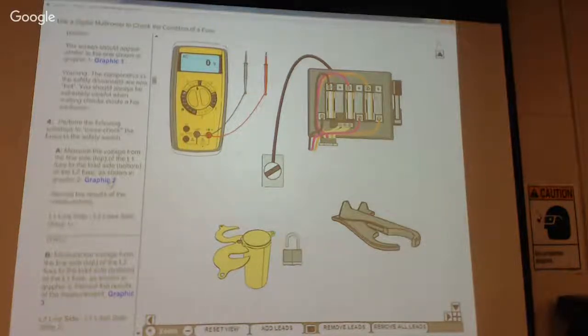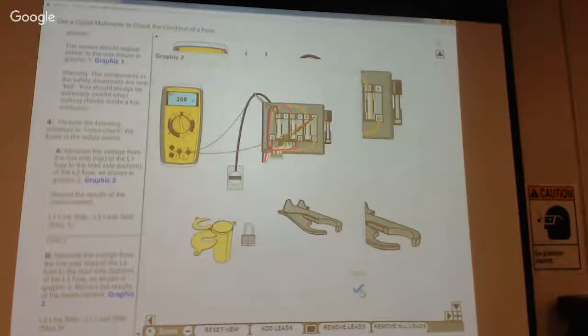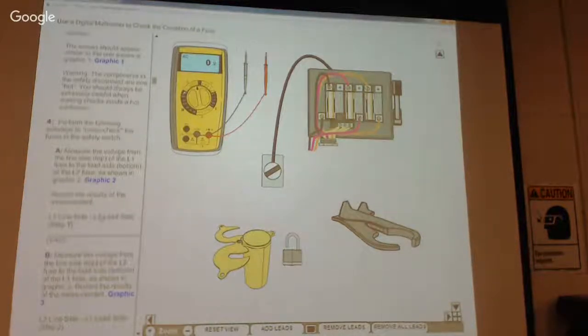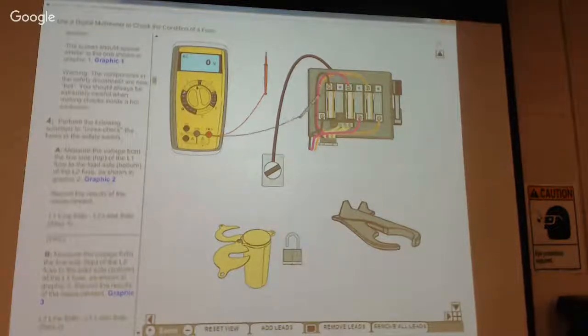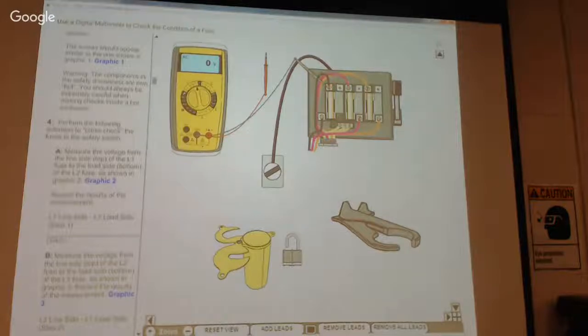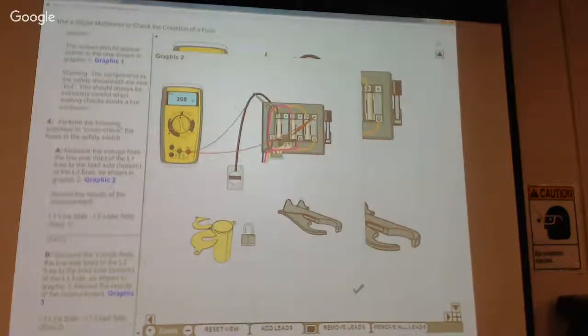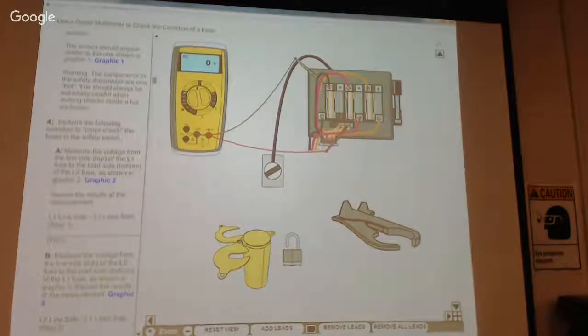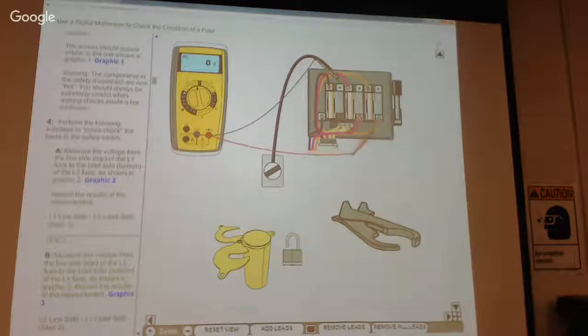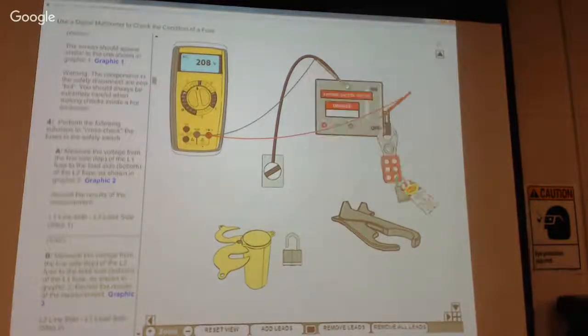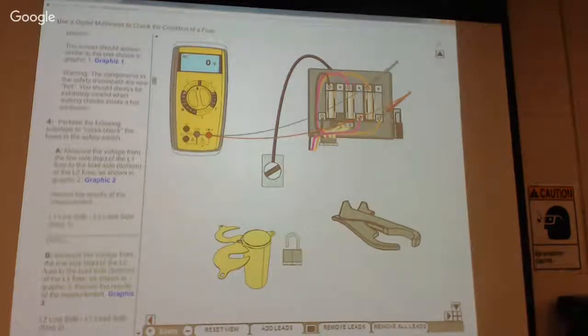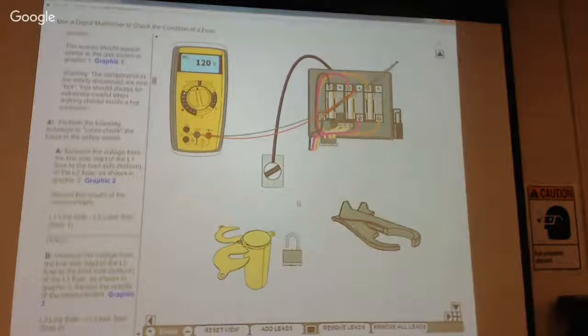And so in graphic 2, they want us to check each one of them, L1 to L2 load side. So we're going to check here. They're going crisscross, checking each fuse. And we're reading 208. All right, we're going to check from here to here. We still have 208. From here to here, and we have 120 volts.